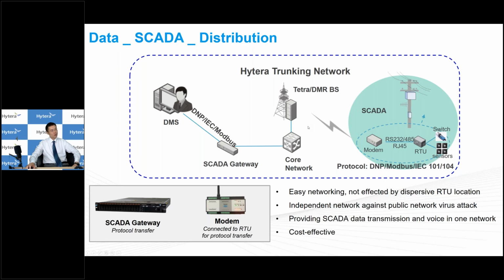Hytera SCADA solution provides remote data monitoring and controlling with a professional SCADA modem for data acquisition and protocol transfer. It supports standard IEC 101, 104, or DNP 3.0 and Modbus protocol. We know 101 is for serial and 104 is for IP technology.